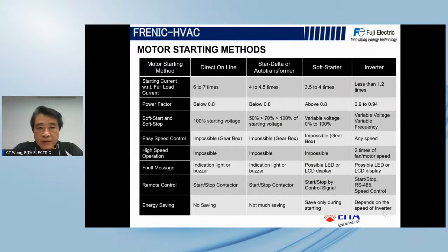High speed operation: for an inverter, you can actually double up the speed if you really want. You can run at maybe 80 or 100 hertz. You are also able to see the fault message. Later, I may go through the protection. Remote control: as I say, with the conventional method you can only start and stop. You cannot get any data on the trip status, or what the overcurrent level is. But inverters can show you the trip message. You can do that by using the RS communication and also the display. Energy saving, later I will touch on that.